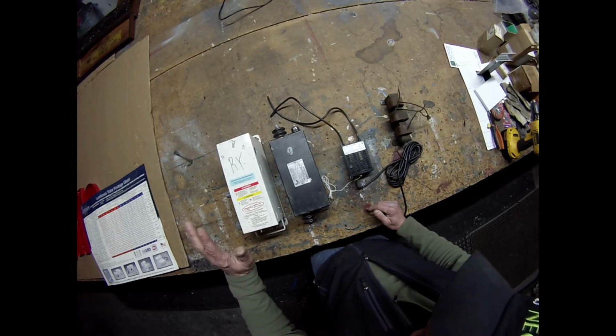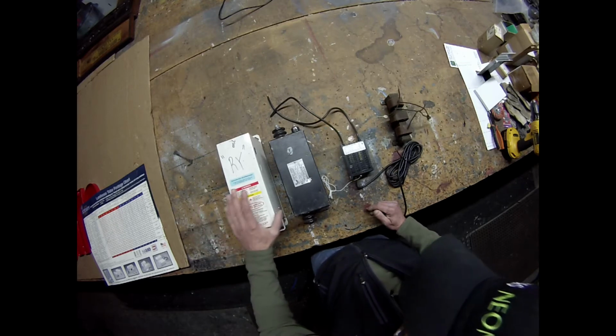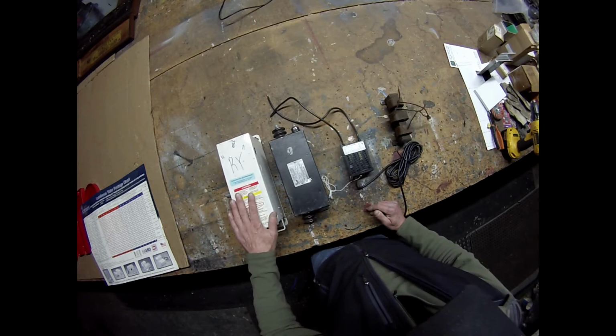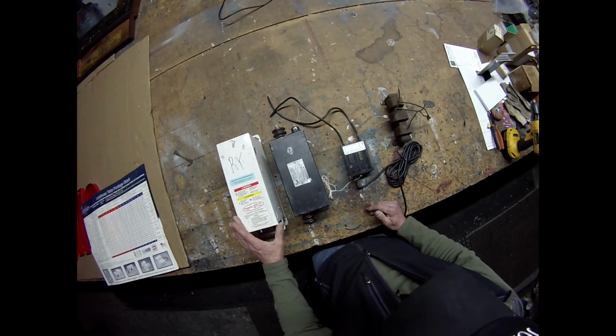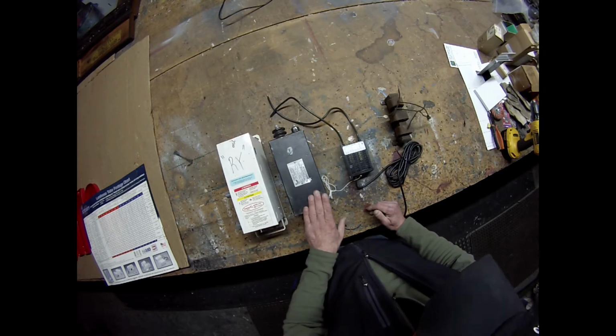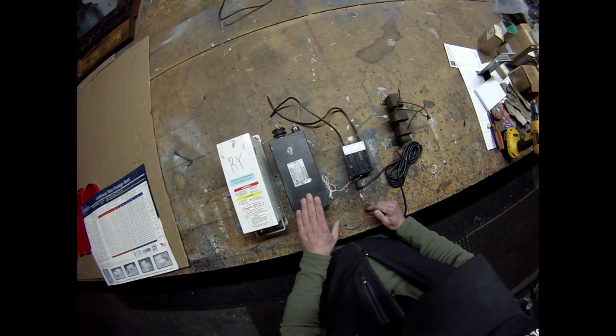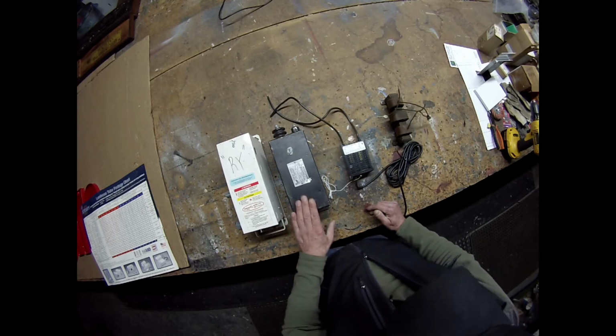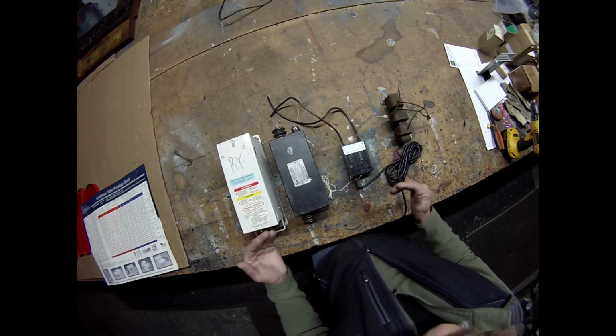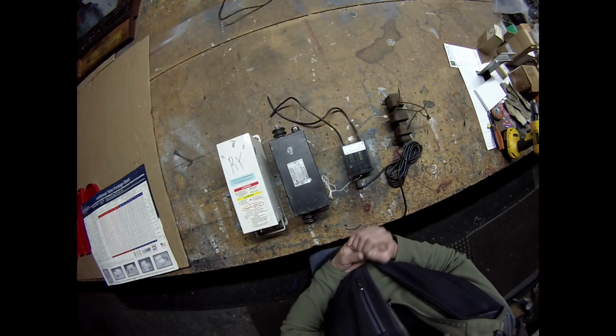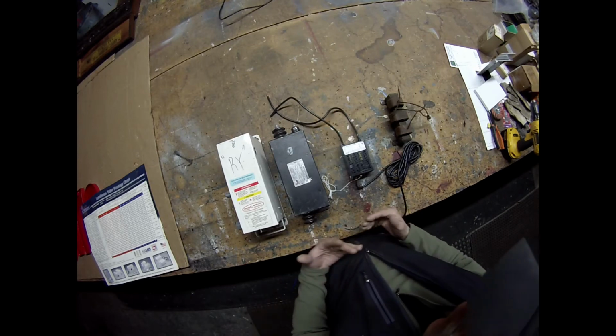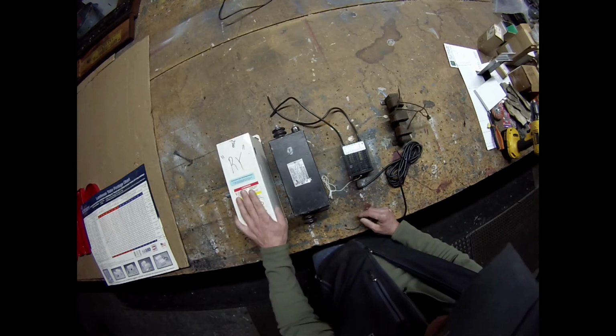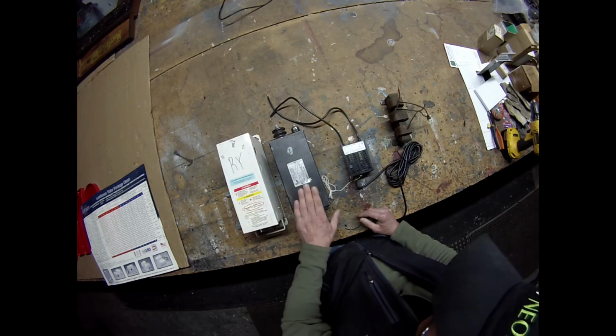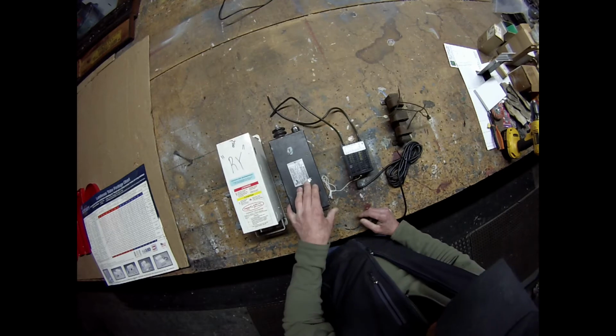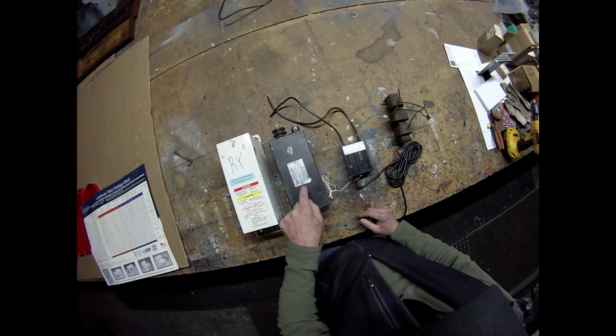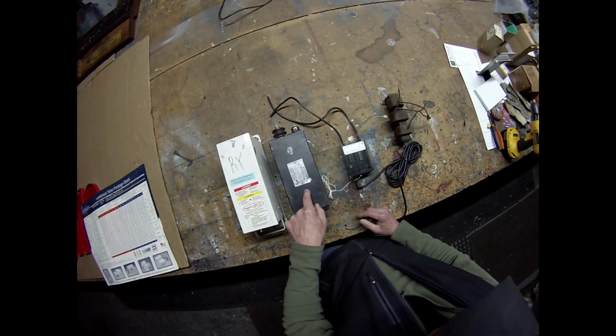So if the neon is having a situation, then this will automatically shut off, and then it has to be manually reset. This transformer here is old school. It will not do that. It will not shut off, and unfortunately these old transformers will cause a lot of problems, including fire, because if there was any kind of arcing or anything going on, they just continue to run. They don't shut off. So these are much more commonly used today than these transformers here. As a matter of fact, I don't even think you can buy a non-smart transformer today, new.